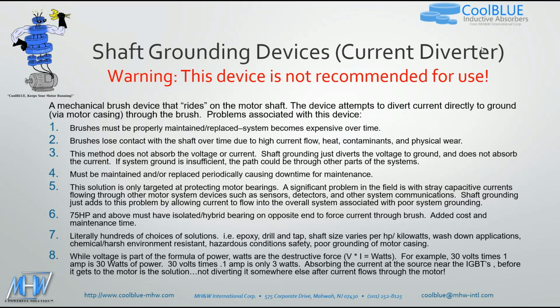You have washdown applications, chemical, harsh, environment resistant, hazardous conditions, and you can have poor grounding of the motor casing. And number 8, while the voltage is part of the formula of power, watts are the destructive force that causes the damage to the motors.